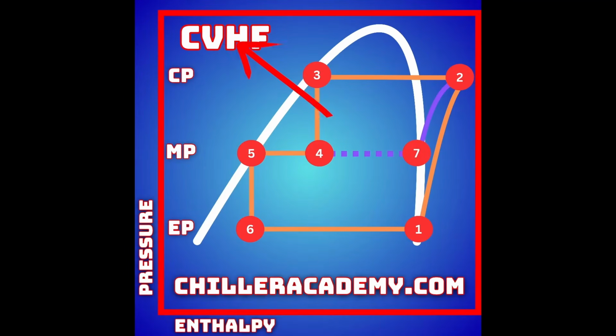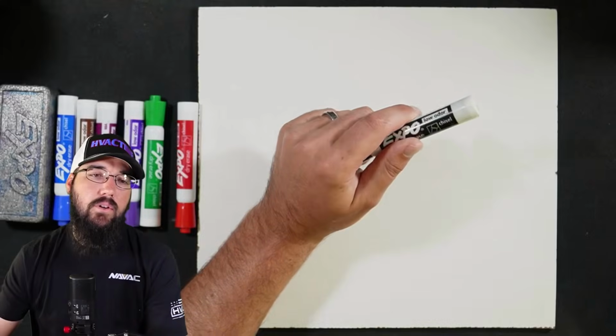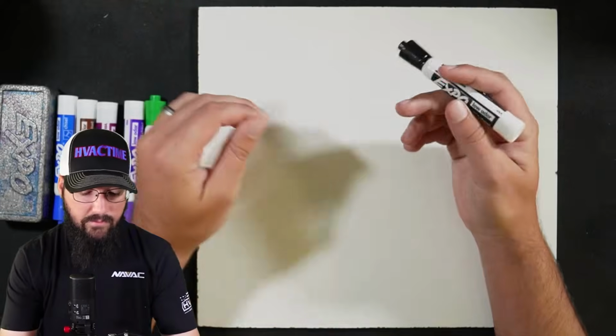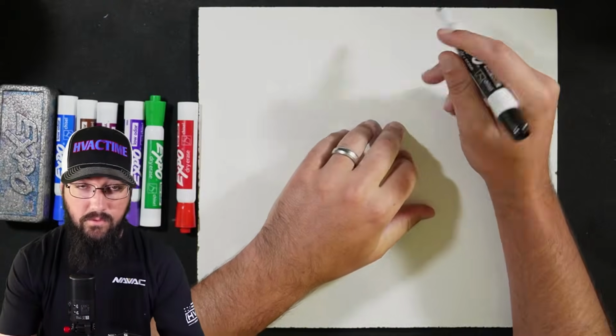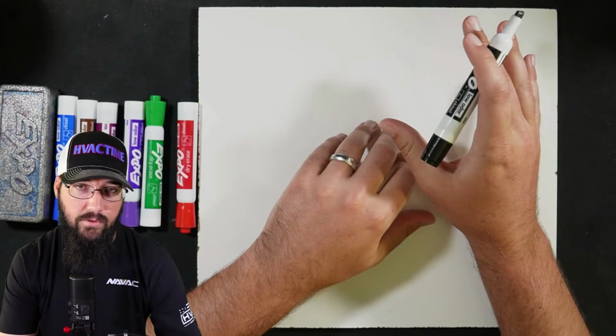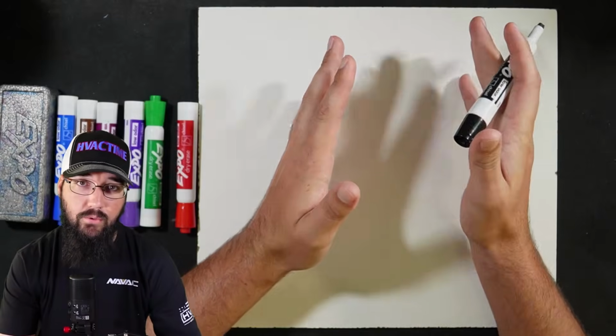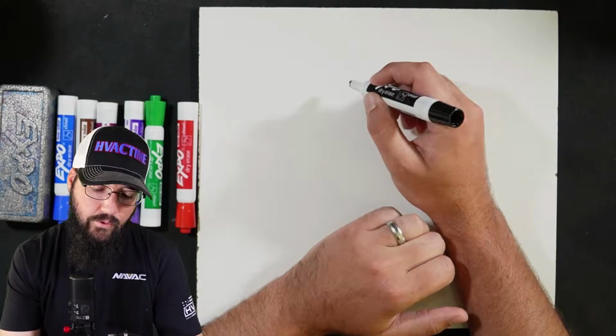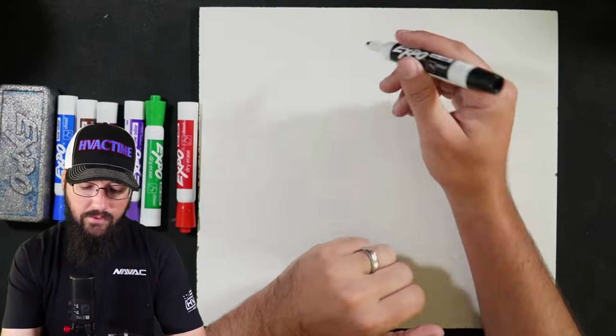Now, I'm just talking about the model of the chiller. So when you look at the model number, the first few letters, for Trane specifically, are the first 4 that you're going to look at. If you have a CV or CD series with an economizer, this is a basic concept we're going to follow. Now, from a refrigerant perspective, let's draw that. So let's continue with the CVHF perspective. The CVHF has 2 impellers instead of 3. We're going to stick with the CVHFs for simplicity.